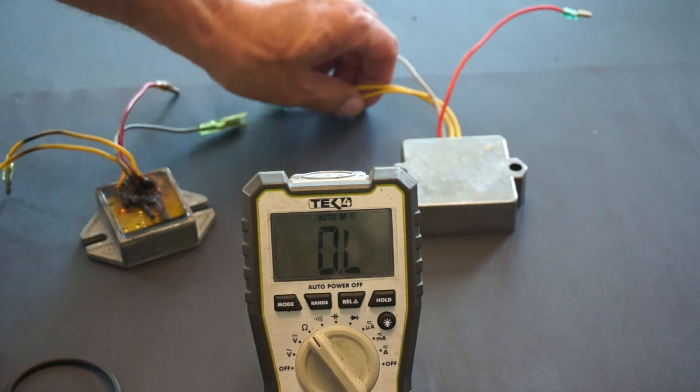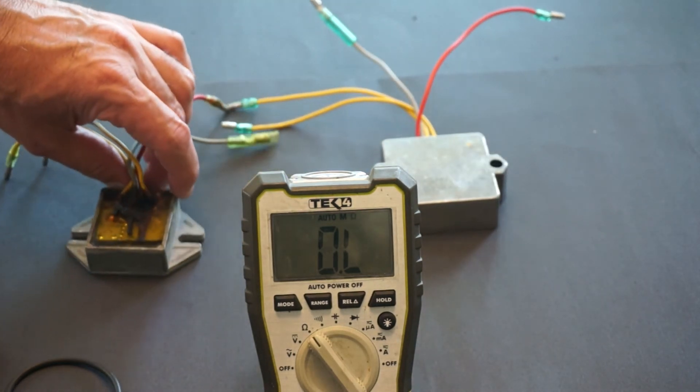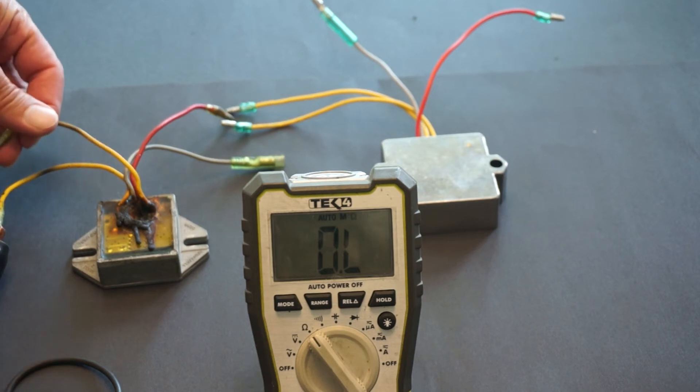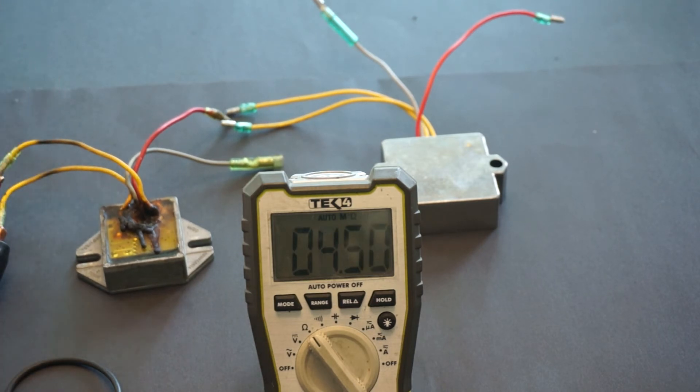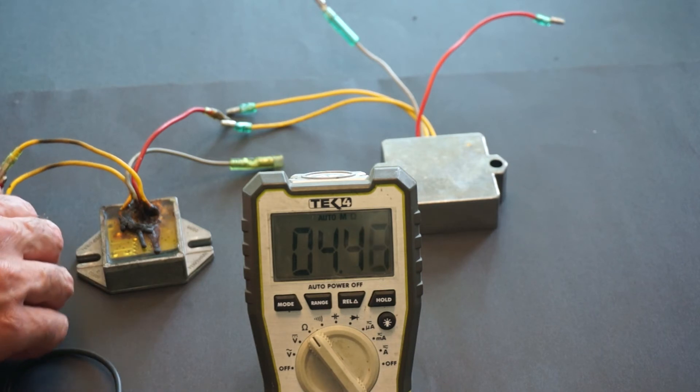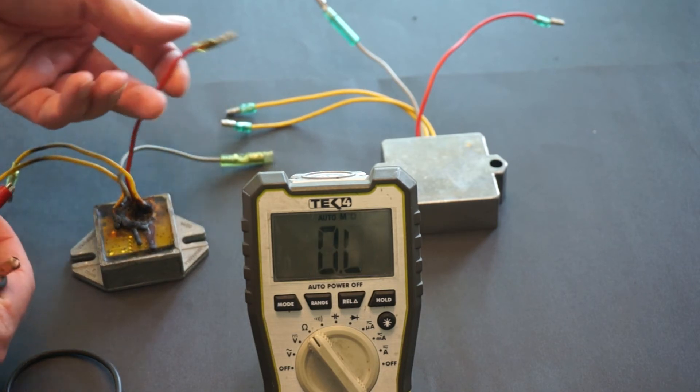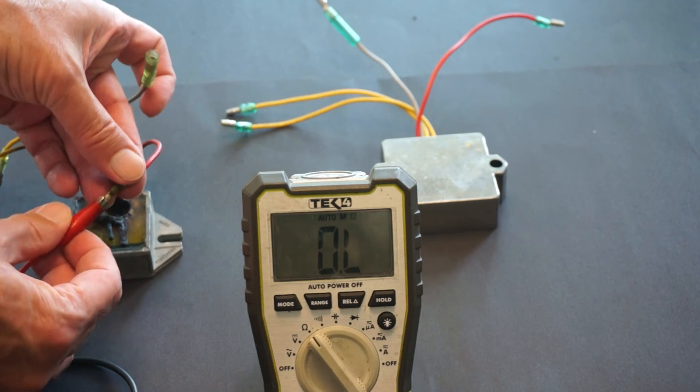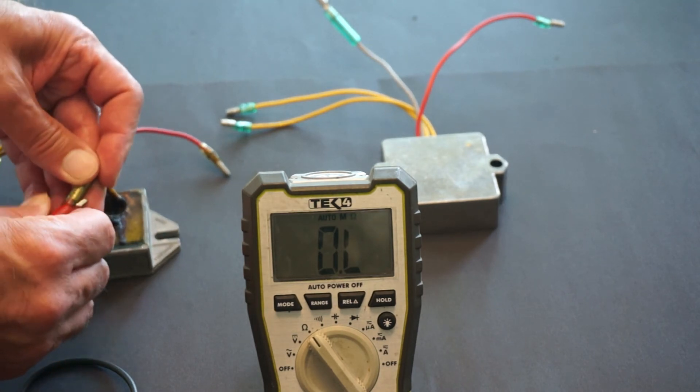Let's take a look at the bad one. The first two wires, the two yellow ones, they read 4.5 meg ohms on the primary circuit and let's see on the secondary circuit.